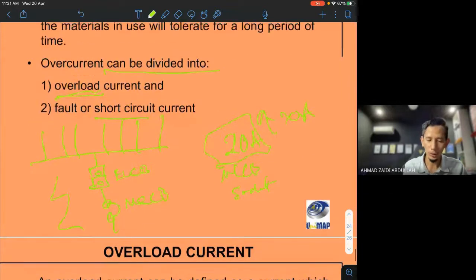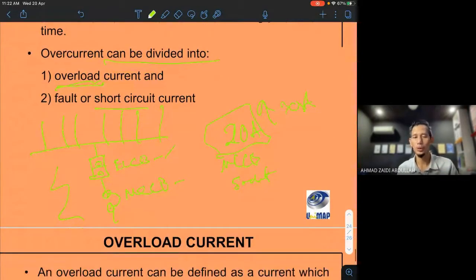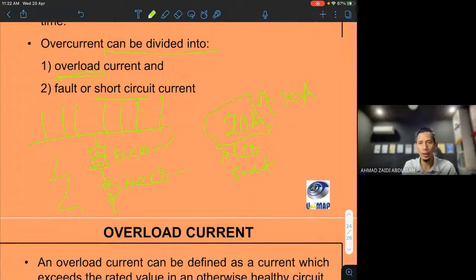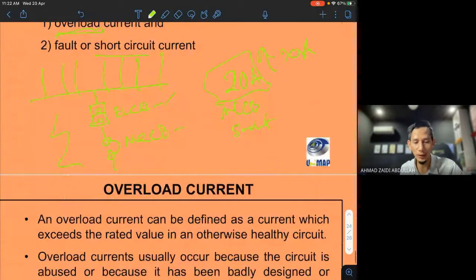Why? Because this part controls the short circuit current, and this part covers the overcurrent, the overload current. That's why we put these two parts in the equipment. Please understand. Later we will look at what the function of the ELCB is, what the difference is, and what the function of the MCCB is. Both are breakers, so can we install just one? Can or not? The answer is no. We must install them separately. But what happened in your house? They installed only one. So after this, please check back your house.